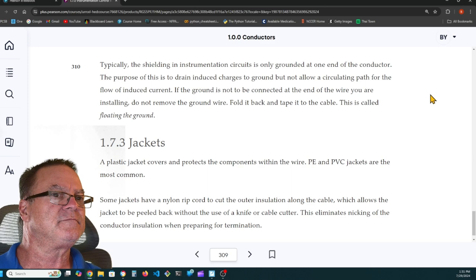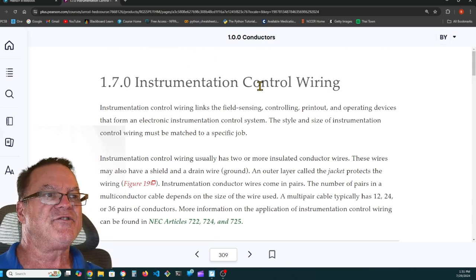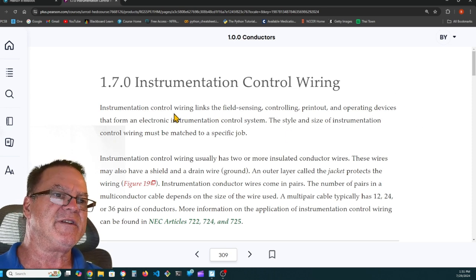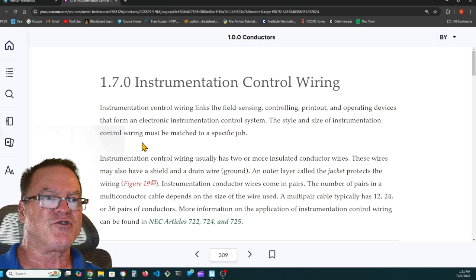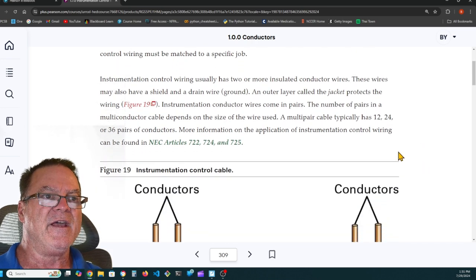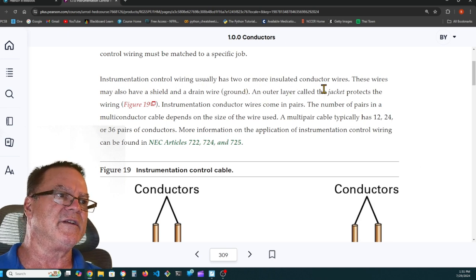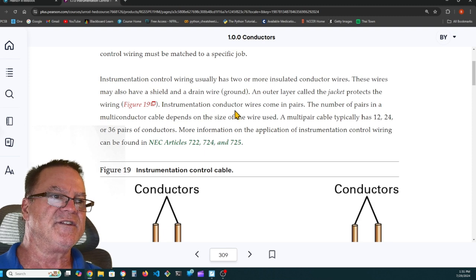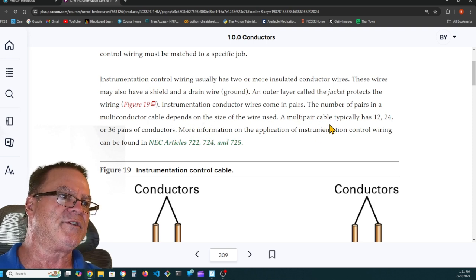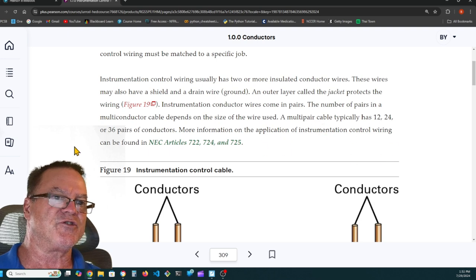Okay, let me move on. Instrumentation control wiring. Instrumentation control wiring links the field sensing, controlling, printout, and operating devices that form an electronic instrumentation control system. The style and size of instrumentation control wiring must be matched to a specific job. Instrumentation control wiring usually has 2 or more insulated conductor wires. These wires may also have a shield and a drain. An outer layer called a jacket protects the wiring. Instrumentation conductor wires come in pairs. The number of pairs in a multi-conductor cable depends on the size of the wire. A multi-pair cable typically has 12, 24, or 36 pairs of conductors. More information on the application of instrumentation control wiring can be found in Articles 722, 724, and 725.